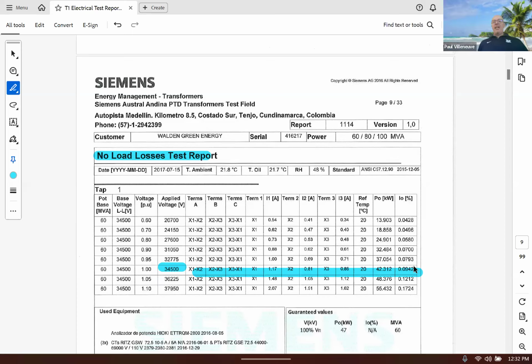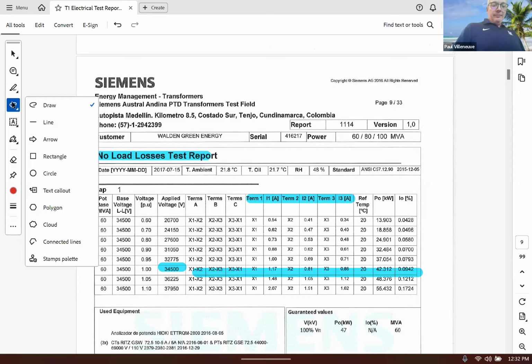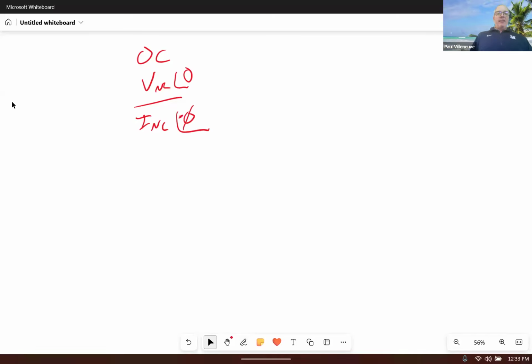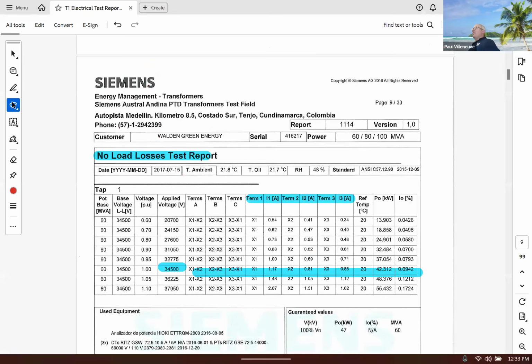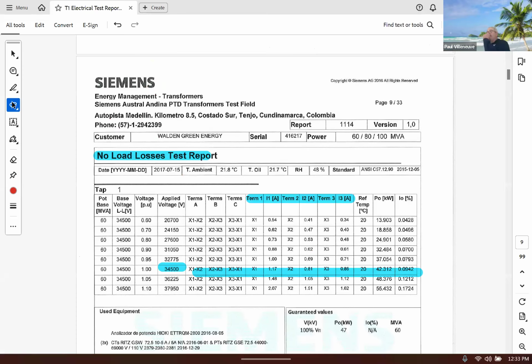Now you can see that I've applied voltage, because it says terminals A, B, and C. It tells you X1 to X2, X2 to X3, X3 to X1. That's where the voltage was applied, okay? And then they measured current flow in those three terminals. The hard part, though, is when I do my open circuit test, or no load test, I need to do V no load divided by I no load, right? This is my angle of Z. This is my angle of negative theta. But I've got three currents there. Which one do I use? I don't know. I just picked the average. So I took the average of those three, came up with my number.